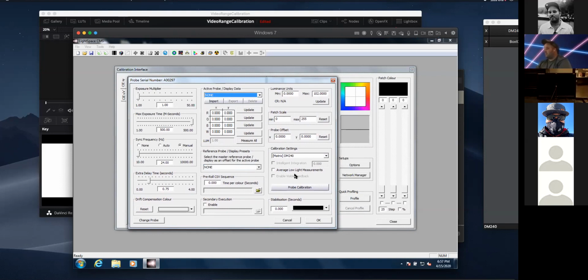So the active probe and reference probe, for those interested, has to do with if you have a probe where you cannot load the matrix onto the probe body directly, you can actually do it within software. So any matrix that I save here from a spectroradiometer-determined matrix for my colorimeter, if I was using something like an I1, I could actually load this as a file or manually enter this information. So what my active probe reads for red, green, blue, white versus what my reference probe measured for red, green, blue, white. So that's a software-based way of doing matrices.